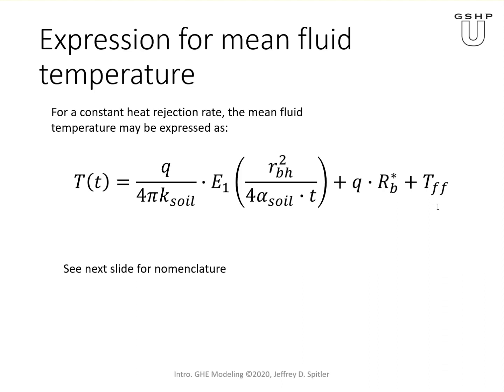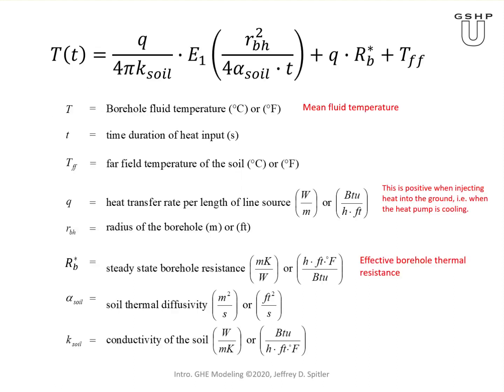Finally, the far field temperature — what I often call the UGT, undisturbed ground temperature — is needed to give us the actual temperature of the borehole wall rather than just the temperature rise. The borehole fluid temperature here is the mean fluid temperature, specifically the simple mean of the entering and exiting temperatures. That's because we're using RB* here; if we just used RB, we'd get the actual mean fluid temperature and would then have to work out the entering and exiting temperatures from there.